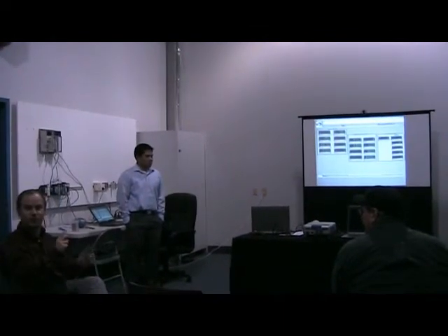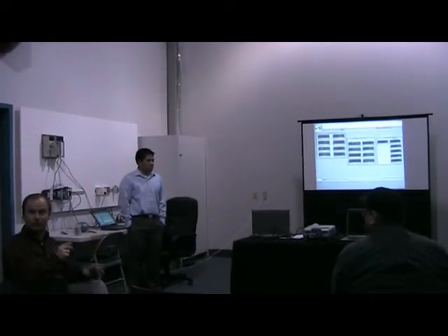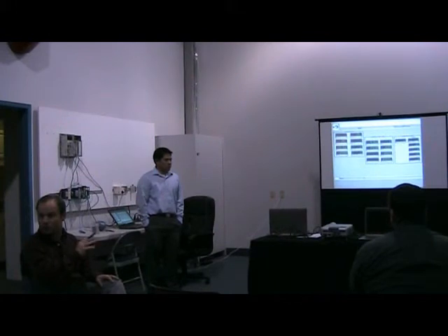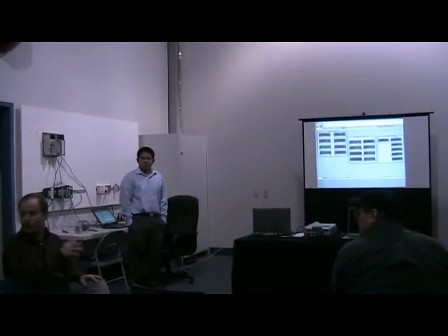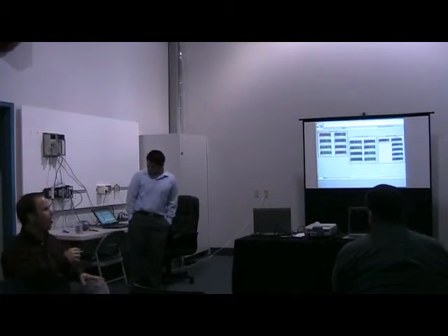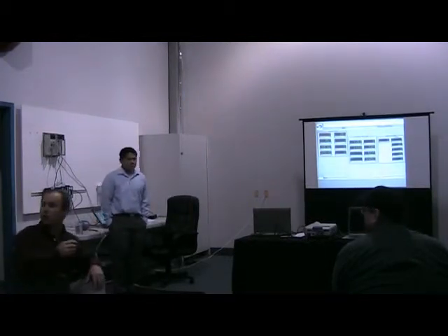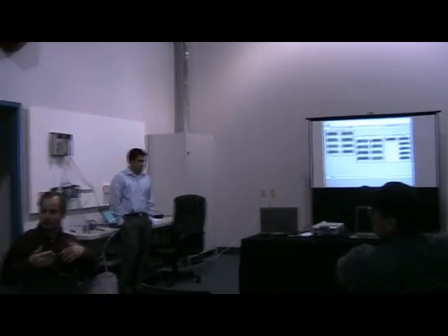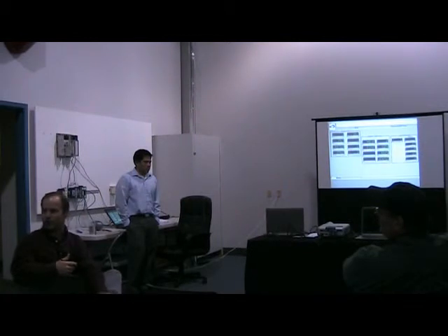However, there is some additional information in versions 6 and 7. It can tell you the last time it was calibrated and give you more specific calibration data. It has historical data stored, I think the last 10, depending on the series. So those are some additional benefits that manufacturers developing their HART modems and devices can also grab.